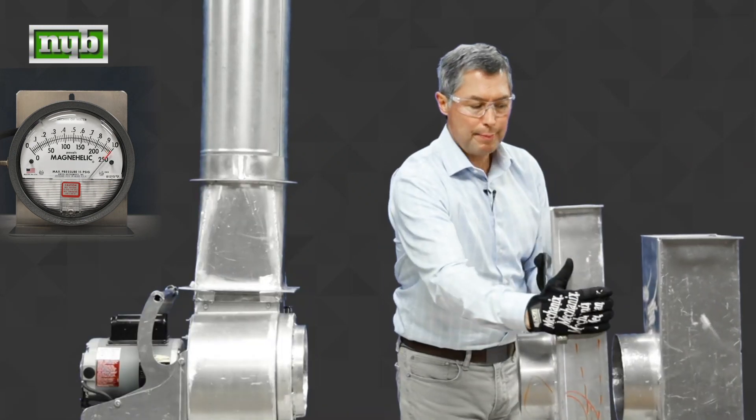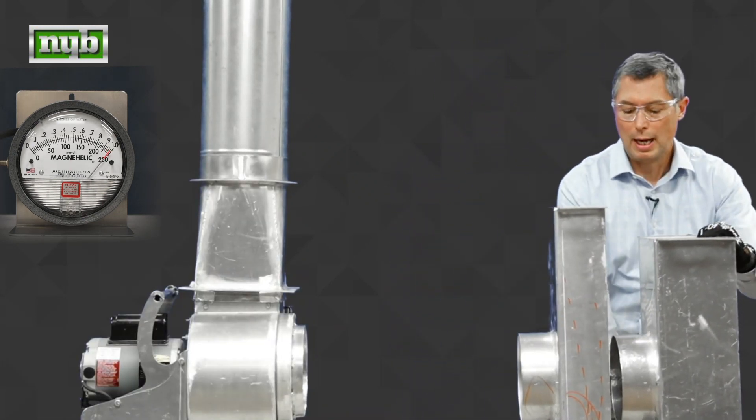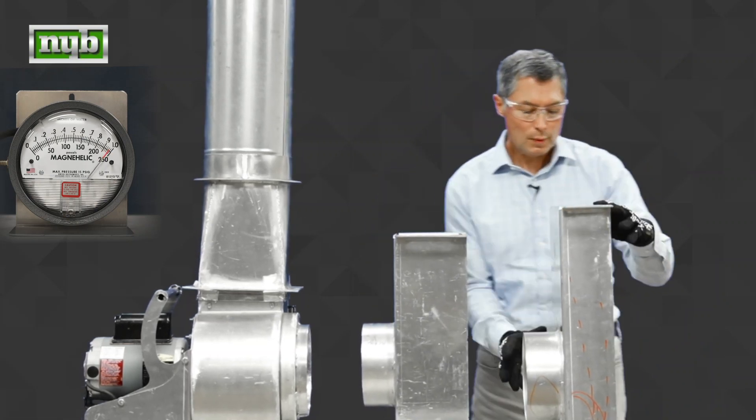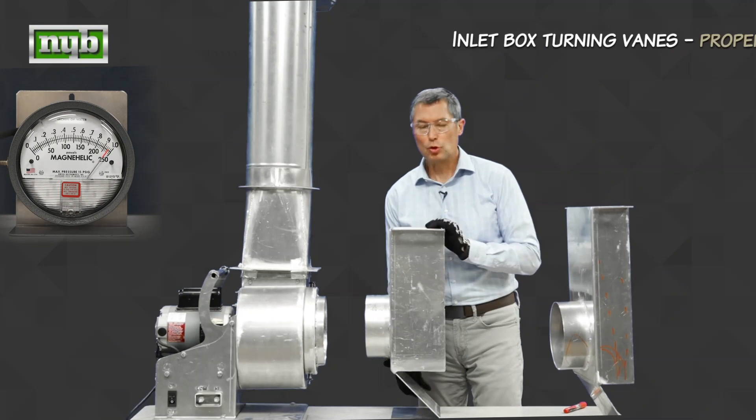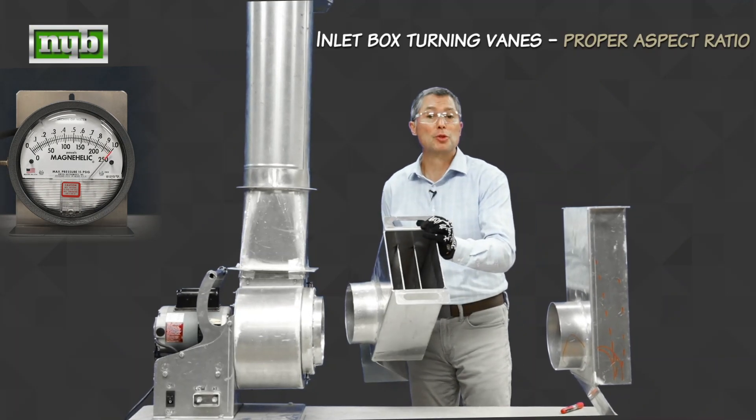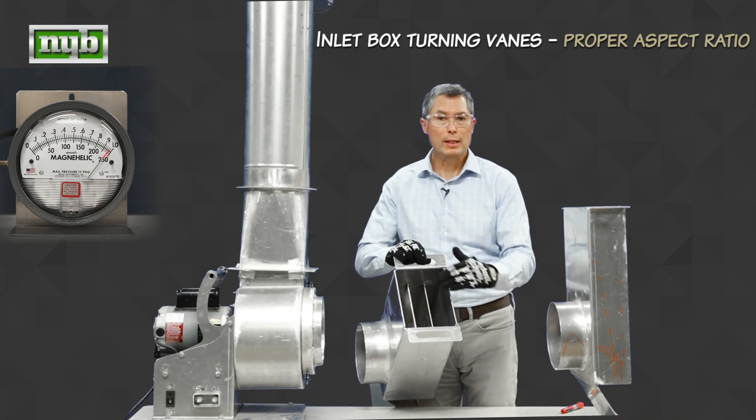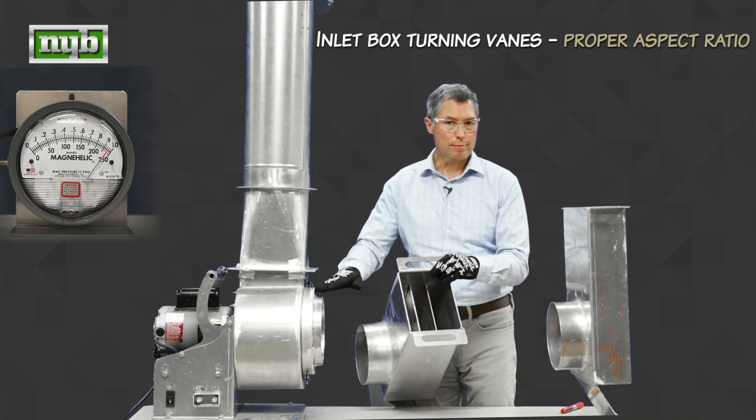Now let's see what happens when we put a proper inlet box on there. Notice that the aspect ratio has changed. Its width compared to its depth is much more square-like. That allows for more air to enter into the box and enter into the fan.